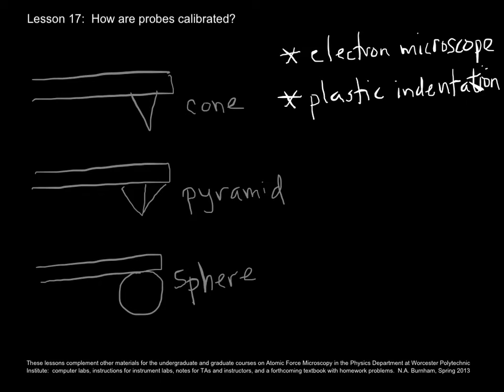Turns out that that's not used too often, because usually the cantilever is at a slight angle with respect to the sample, and this means as you indent, you also slide horizontally a little bit as the force becomes bigger. And this means that your hole is not a perfect hole, it's more like a streak. However, it's still a good option if your own AFM has a horizontal cantilever with a vertical tip. That's perfectly normal to the sample surface.